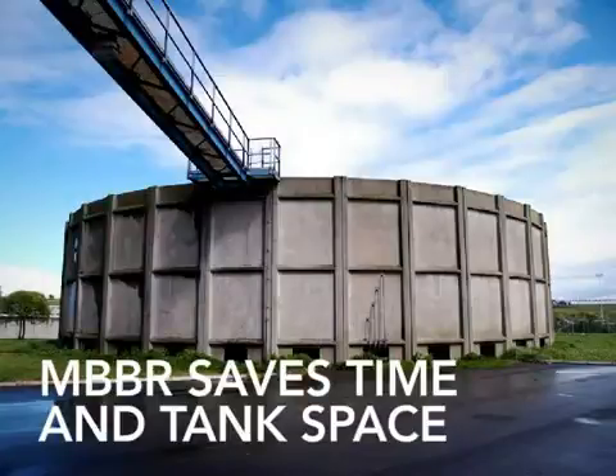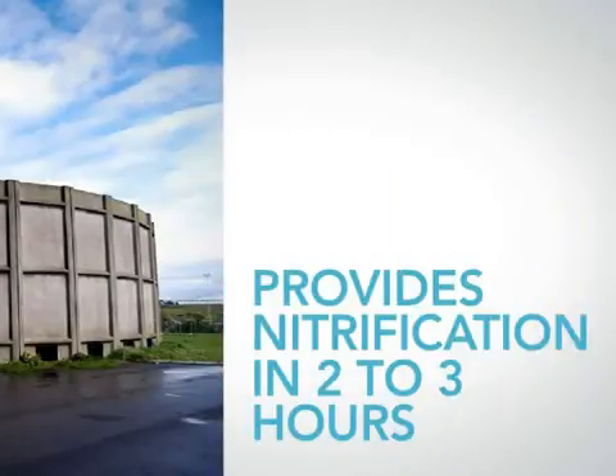Whereas activated sludge is designed for 12 to 24 hours of hydraulic retention time, MBBR needs only 2 to 3 hours to achieve the same level of nitrification, using a quarter or less of the tank volume.